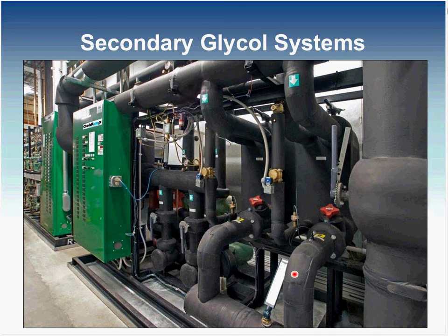That means your harmful refrigerant is only staying in the back room. It's not being piped at all out to the sales floor to any of the display cases. So since it's in the back room, it's obviously not leaking through all of your piping in your display cases. That's correct. It's really all confined in one spot. You may have some condensers up on the roof to get rid of heat outside the building. But primarily, all of your refrigerant is right in this room, from where you see the chillers over here all the way down to the other end, which is the end of your compressor rack. This is where the refrigerant is, and this is where you need to look for leaks and do things like that.